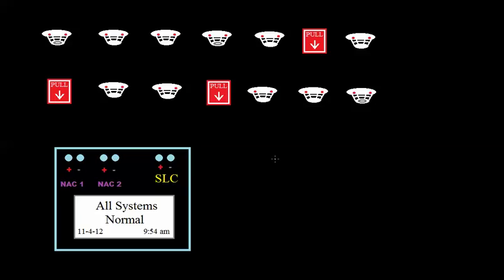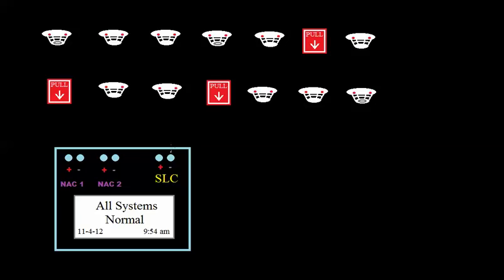On the right, you can see I've drawn this little circuit here, and it's labeled SLC, and that stands for Signaling Line Circuit. That's a terminology that a lot of manufacturers use, not all of them. Simplex and I think Edwards use some other ones, but the panels I primarily deal with use that terminology. They all use some form of data communication with their devices. But whatever they call that may vary from manufacturer to manufacturer. For all of our initiating devices, we can use just this one data loop.